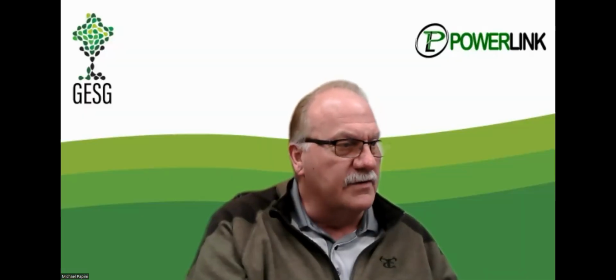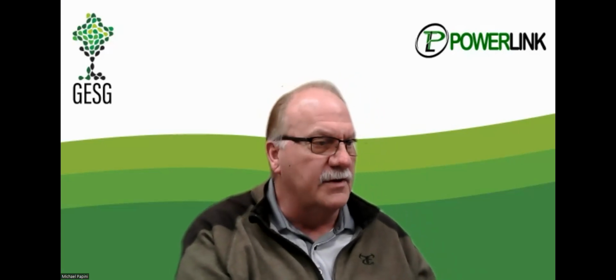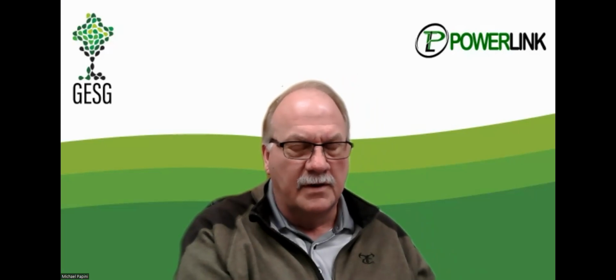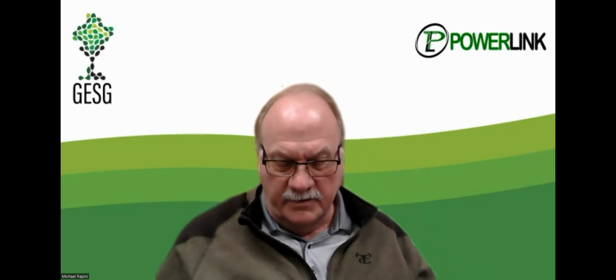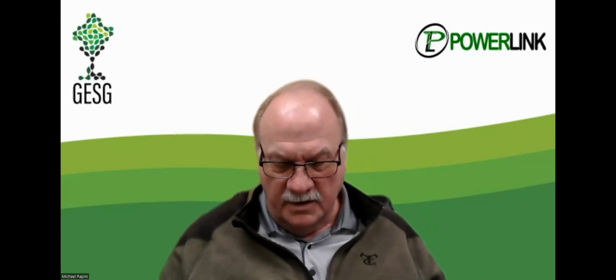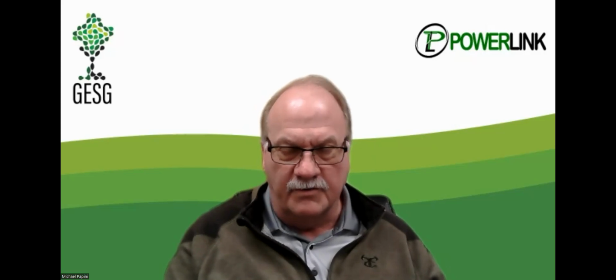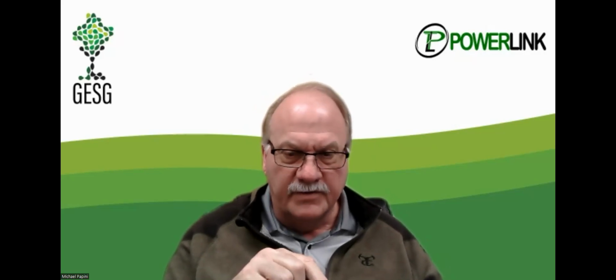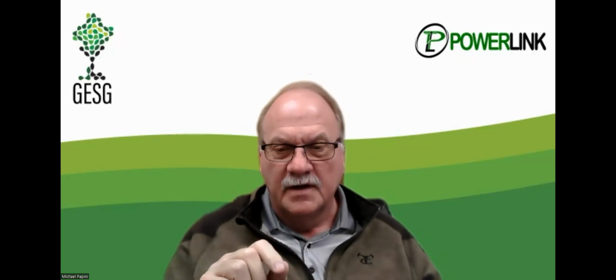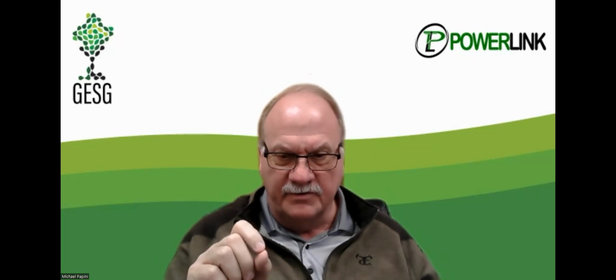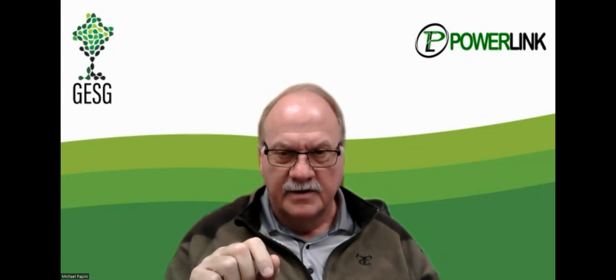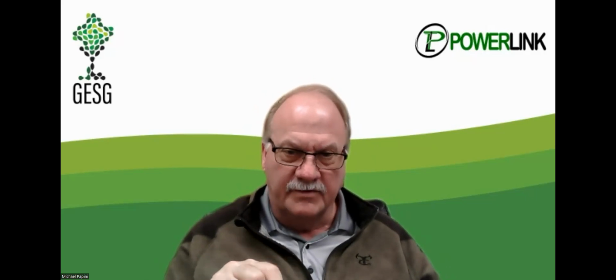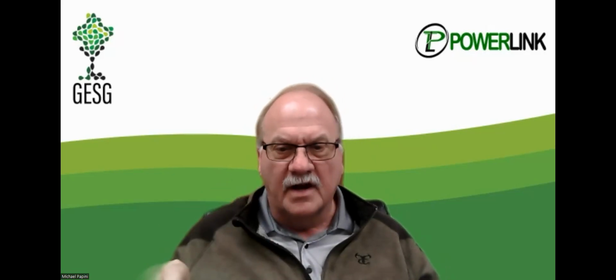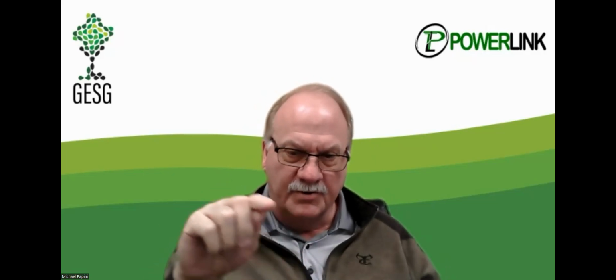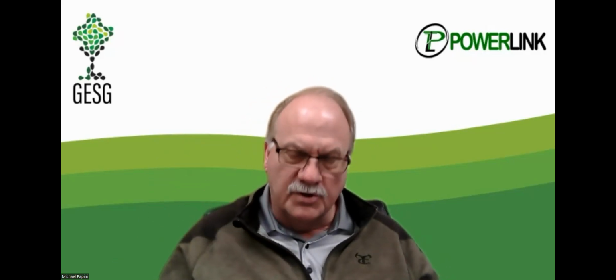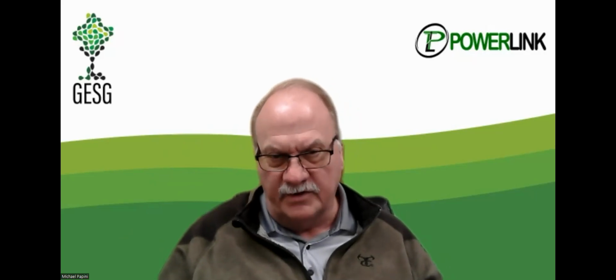Yeah, a harmonic is a different frequency that's on your electrical system. Right now, you're at 60 hertz. A 5th harmonic is very easy to figure out: if you take the 5th harmonic times 60 hertz, it's 300 hertz. So that wavelength is traveling back and forth on that same piece of wire that's at 60 hertz, which means it goes plus and minus 60 times a second. At 300 hertz, it goes plus and minus 300 times a second. What it does is distort that sine wave, the voltage part of it. It kind of pyramids it out instead of being round, so your voltage goes down in those cases. It's called transients on the system.